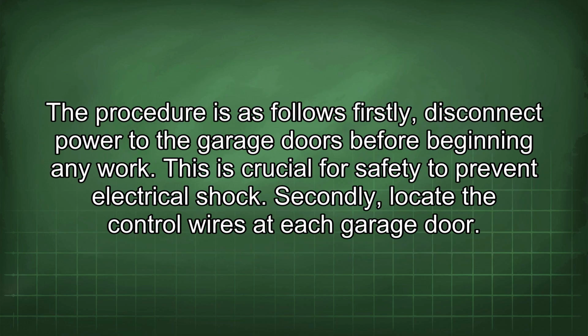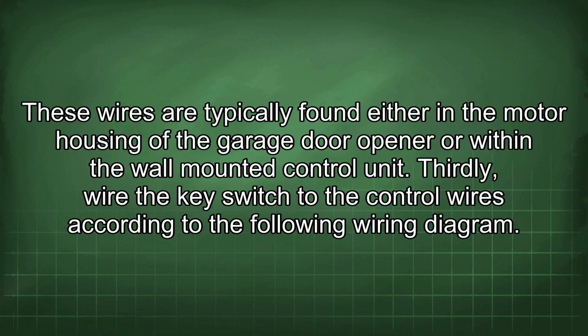Firstly, disconnect power to the garage doors before beginning any work. This is crucial for safety to prevent electrical shock. Secondly, locate the control wires at each garage door. These wires are typically found either in the motor housing of the garage door opener or within the wall-mounted control unit. Thirdly, wire the key switch to the control wires according to the following wiring diagram.